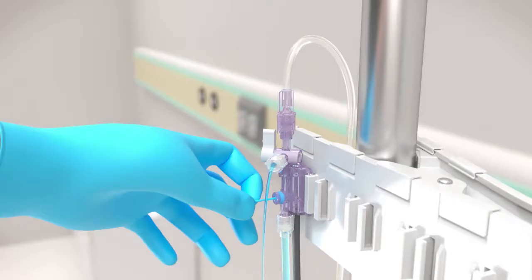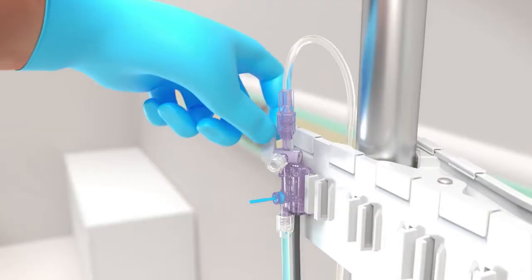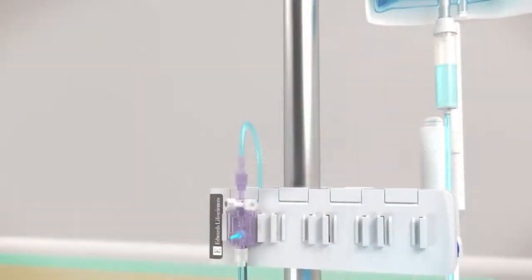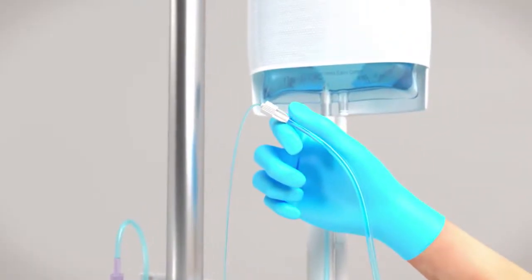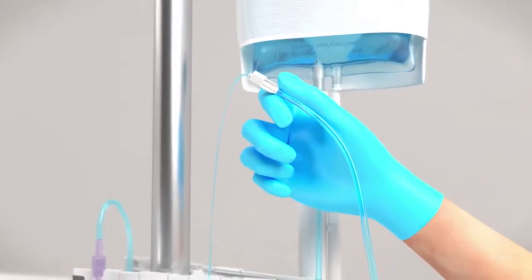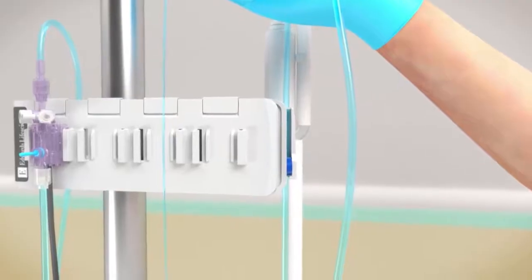Remove all air bubbles. Close the vent port by turning the stopcock toward the cap. Holding the pressure tubing in an upright 45-degree angle, pull the snap-tab to flush the remaining part of the line through the end of the tubing. Visually inspect the line to ensure that all air bubbles are removed.